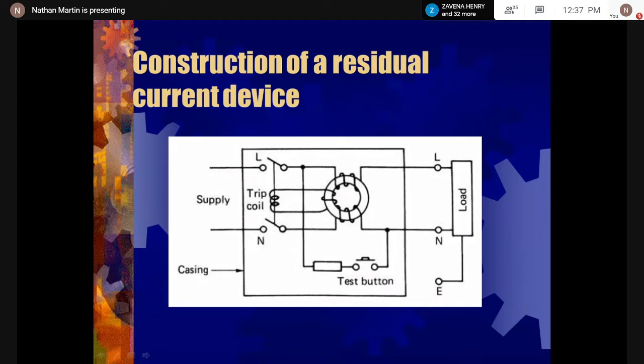No. When you wire this device, for persons who are aware of it, the device comes with an earthing terminal. The breaker comes with an earthing wire that you carry directly to the earth bar in the panel. This is why the earth is critical. The device operates on earth fault only. So when you have a short circuit between line and earth taking place, you are going to have a leakage current, right?